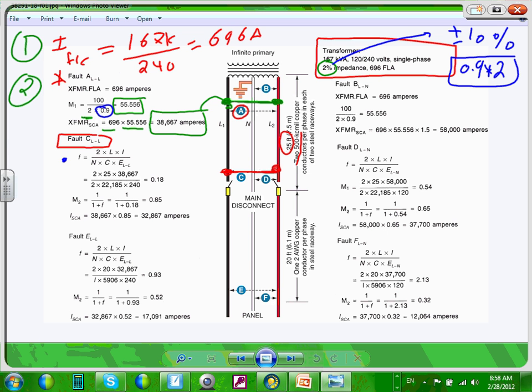Where's the I? I is the short circuit right at the terminal of the transformer. Everybody can see that I is the short circuit right at the terminal of the transformer. N is the number of conductors in parallel. How many conductors do I have in parallel, guys? 2 conductors. C is the factor. We're going to find this C in a second. And ELL is the voltage line to line.